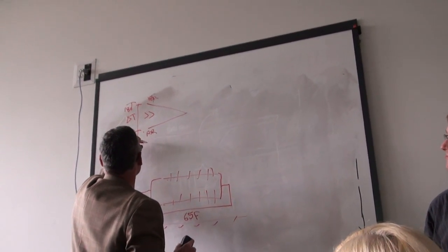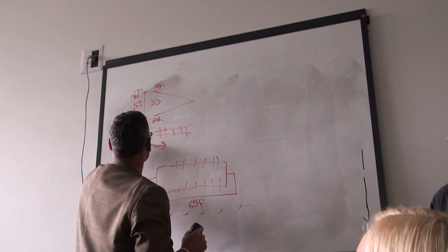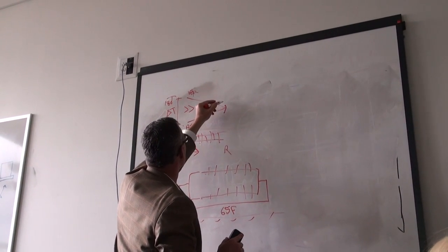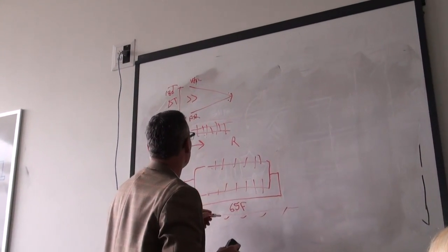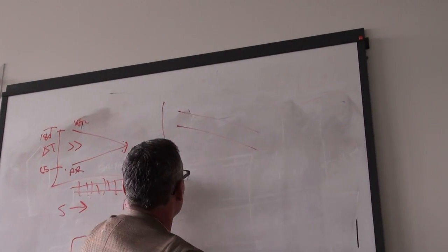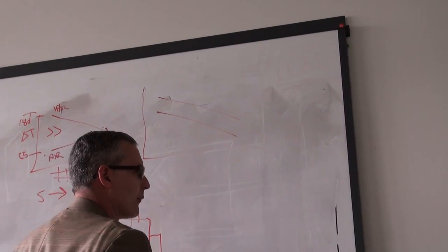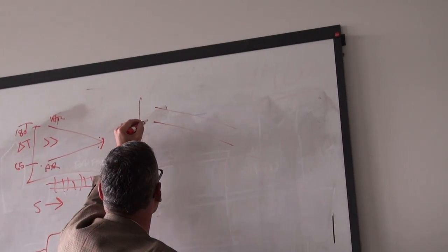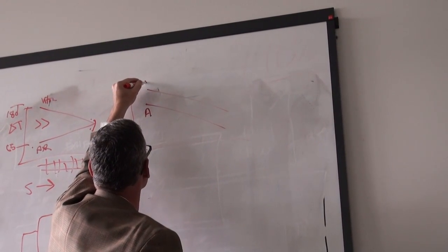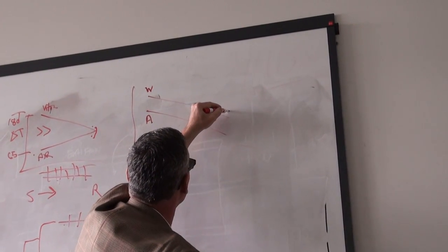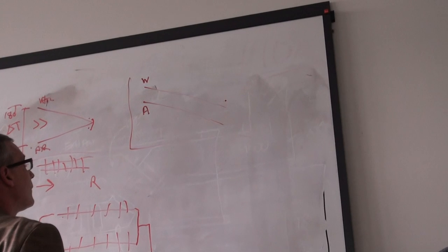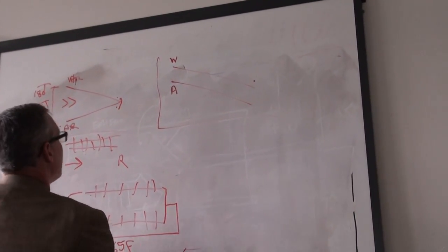This is the beginning of the fin tube, and this is the flow of the water, supply to return. At the end, you get very little heat transfer because the temperature of the water is cold and the temperature of the air is warm. The more optimum way to transfer heat, using a log mean temperature difference, is to take your warmest air and your warmest water to interface, and your coldest water and your coldest air to interface. So you get a nice even delta T across this.